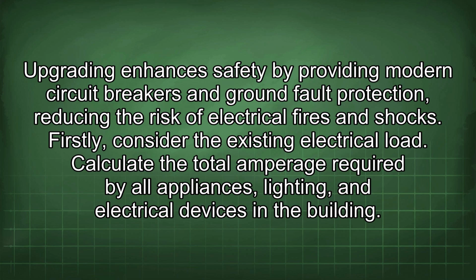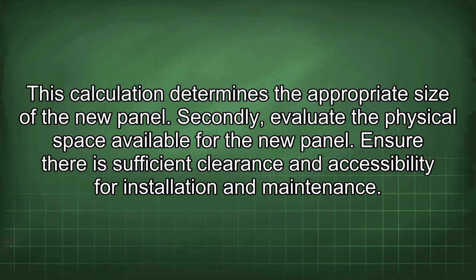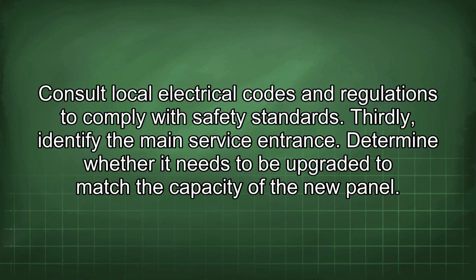Firstly, consider the existing electrical load. Calculate the total amperage required by all appliances, lighting, and electrical devices in the building. This calculation determines the appropriate size of the new panel. Secondly, evaluate the physical space available for the new panel. Ensure there is sufficient clearance and accessibility for installation and maintenance. Consult local electrical codes and regulations to comply with safety standards.